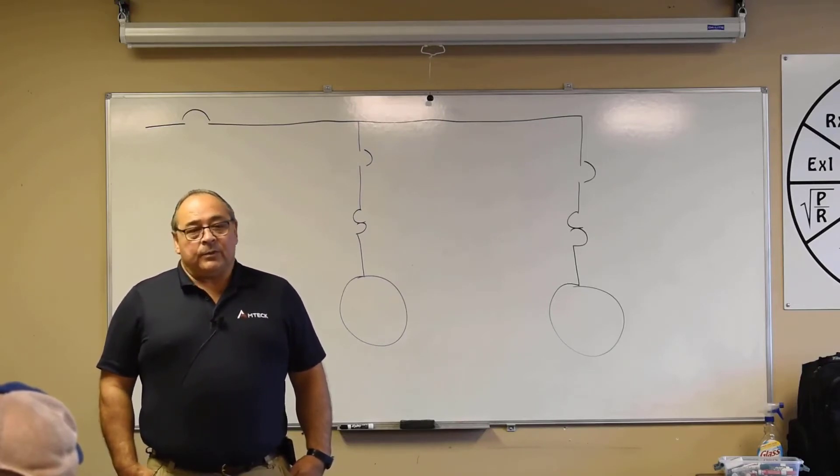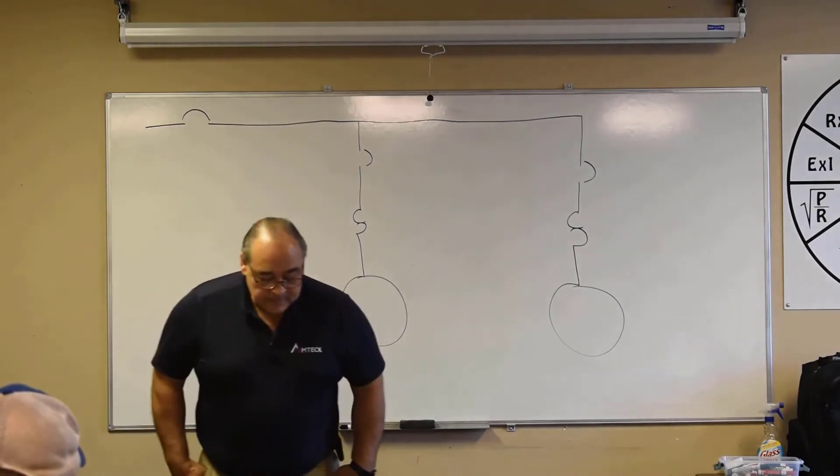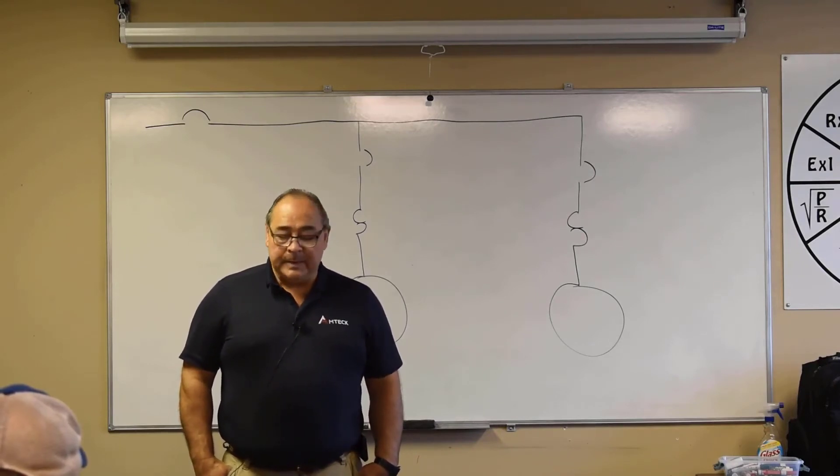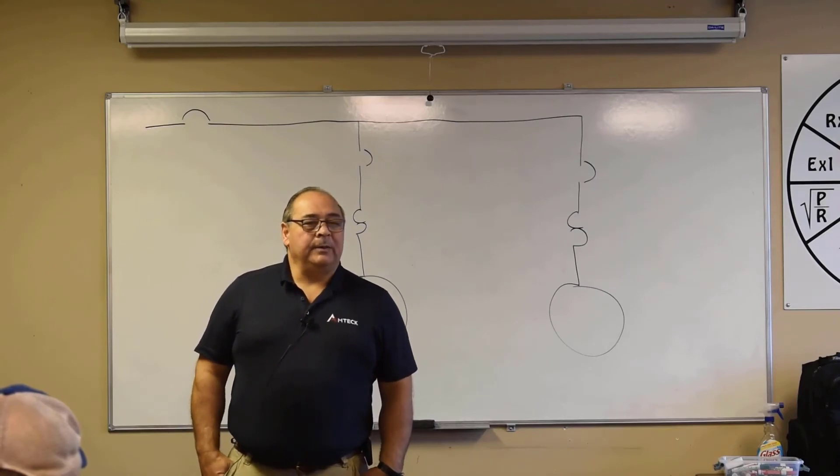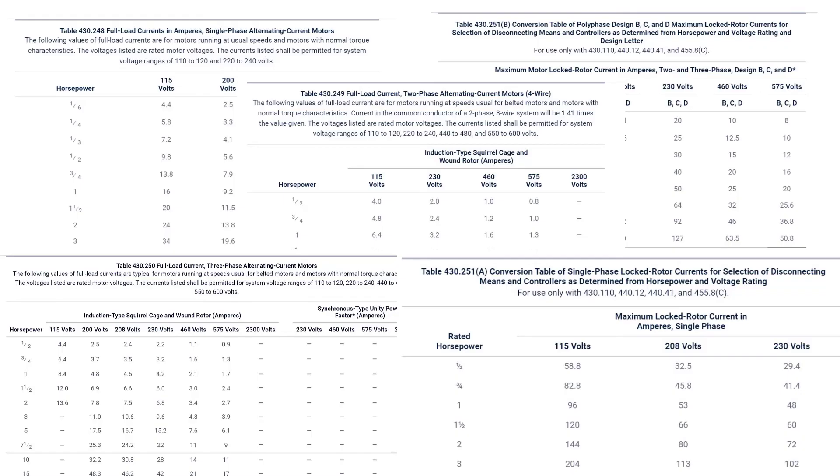So I want you guys to understand that and make this easier to handle. When I'm telling you we're going to put a number 12-gauge wire on a 100-amp breaker, you say, no, that's illegal. No. For motor circuits, it's not. You're going to fight with yourself. Those are the guys that's got all the experience and knowledge in this room. You're going to fight with yourselves. Well, I wouldn't put a 12-gauge wire on a 100-amp breaker. You can't make me do it. Well, that's the right answer on test day. So, we start this process by looking at these tables.